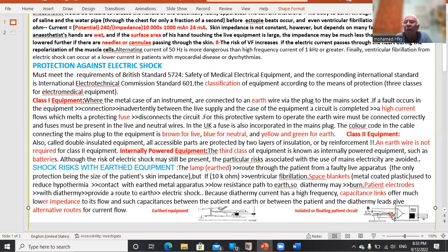This figure is not present in the new edition of Barash, but is present in the old one. I will show it later, where we have what we call a neutral electrode. This neutral electrode, to avoid interference, is, as you can see, not attached to the main component. It is floating. So this is a method to avoid electrocution whenever I use a neutral electrode with this new type of electrical equipment.